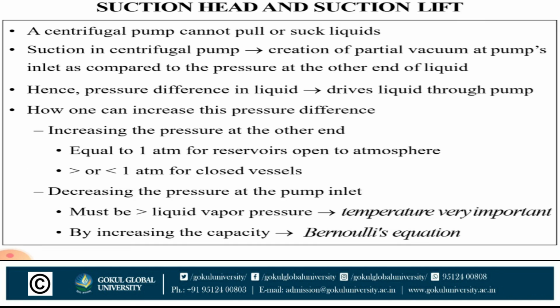Suction head and suction lift. A centrifugal pump cannot pull or suck liquid. Suction in a centrifugal pump is the creation of a partial vacuum at the pump's inlet as compared to the pressure at the other end of the liquid. Hence, the pressure difference in the liquid drives the liquid through the pump. How can one increase this pressure difference? Increase the pressure at the other end, equal to 1 atmosphere when the reservoir is open to atmosphere. Decrease the pressure at the pump inlet, which must stay above the liquid vapor pressure, so temperature is very important.